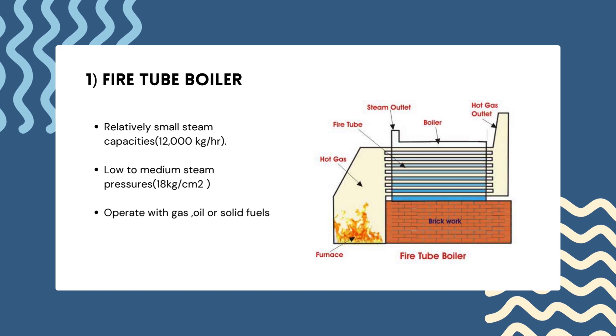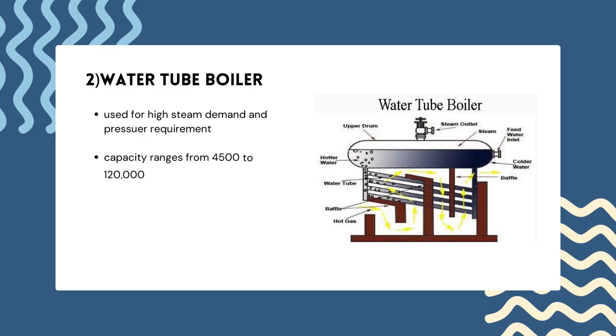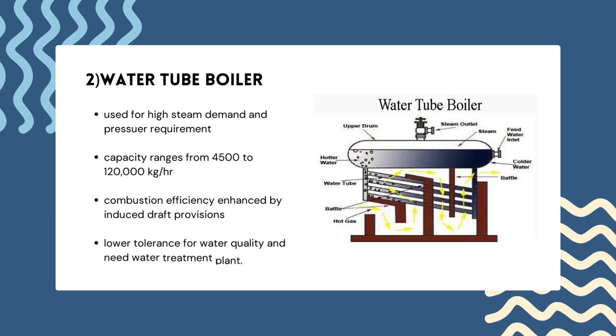Fire tube boilers operate with oil, gas or solid fuels. The second type is the water tube boiler, where water is heated inside tubes and the hot gases surround them — the opposite of a fire tube boiler where hot gases pass through tubes surrounded by water. Water tube boilers are used for high steam demand and pressure requirements. Their capacity ranges from 4,500 to 120,000 kg per hour. Combustion efficiency is enhanced by induced draft provisions, though they have lower tolerance for water quality and require a water treatment plant.